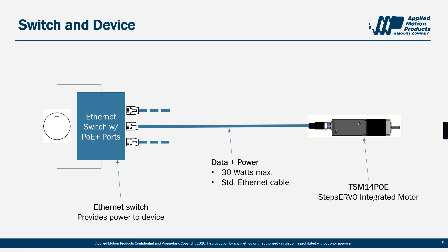PoE Plus delivers up to 30 watts per port using standard Ethernet cable. We recommend Category 6 cable for most installations. The only things you need to take advantage of PoE are compatible devices on both ends of the network connection — on the power supply side, you'll have an injector or a switch, and on the device side, you'll have a TSM-14 PoE step servo integrated motor. We'll talk more about injectors and switches in a bit, but for now I'd like to focus on the integrated motor.